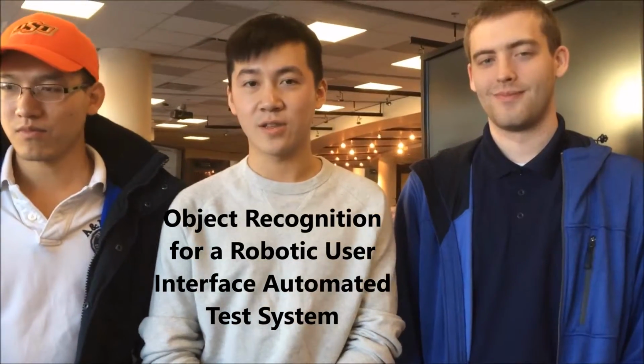So we developed an automatic test system for a medical device by using a camera to capture an image and process it through our computer and control the product to push a button.